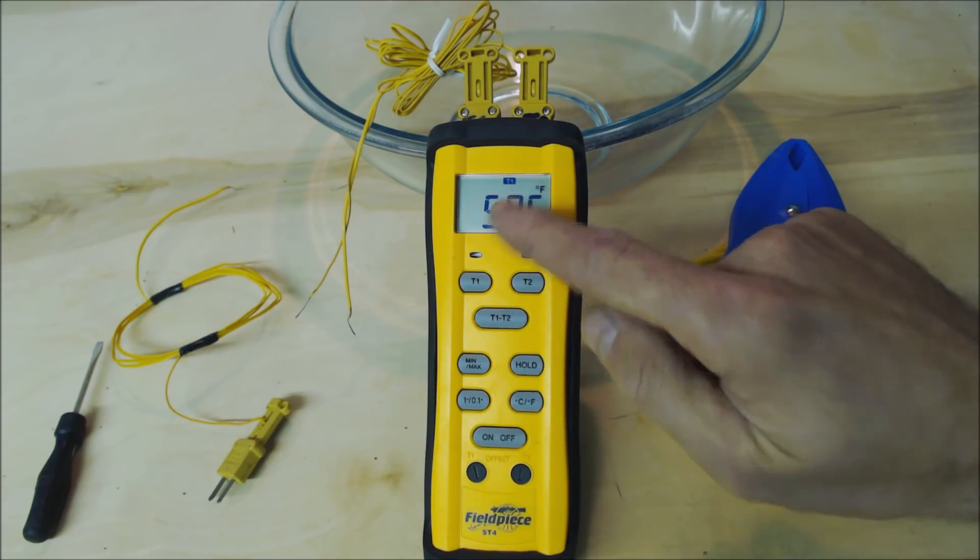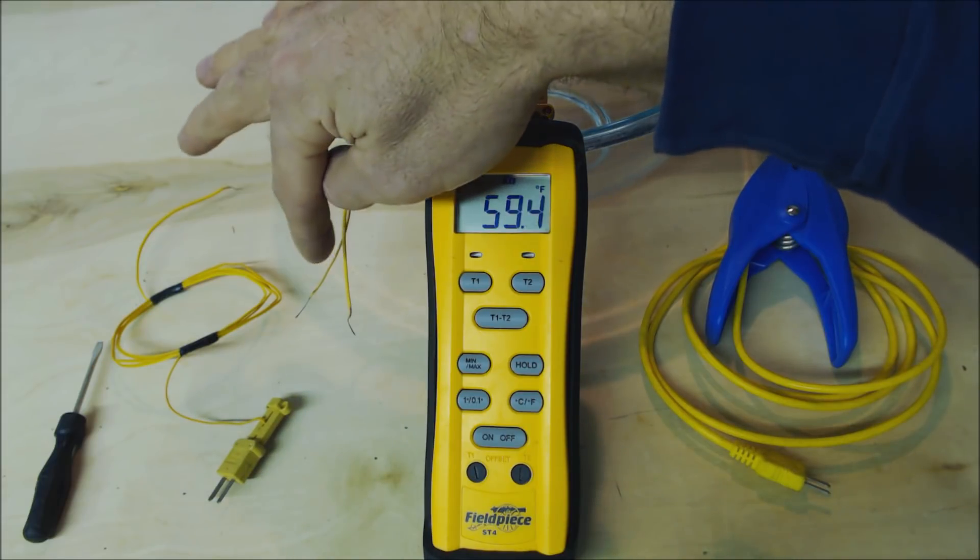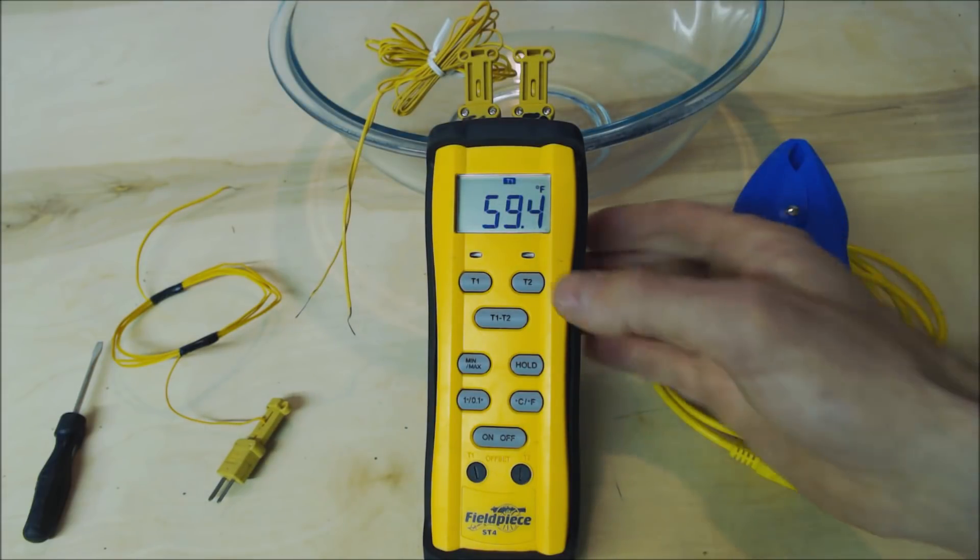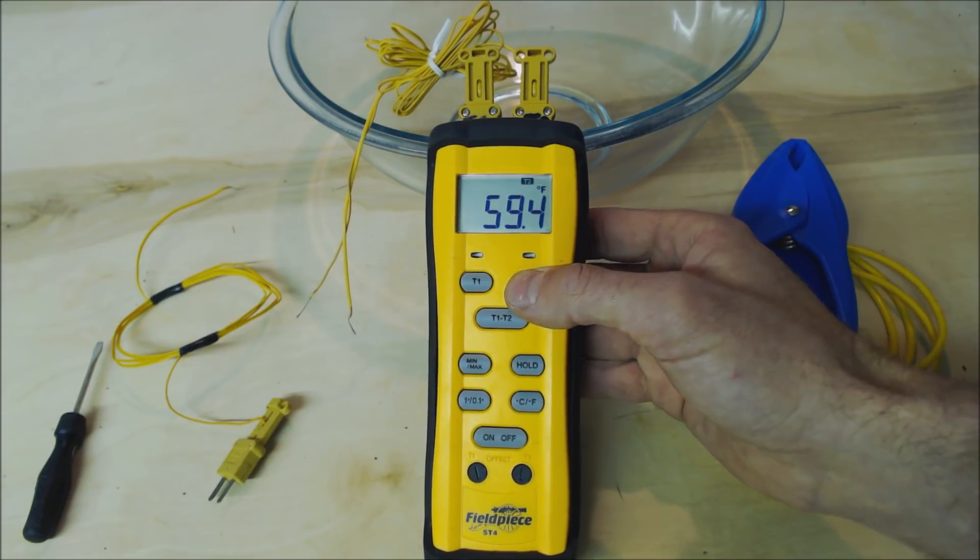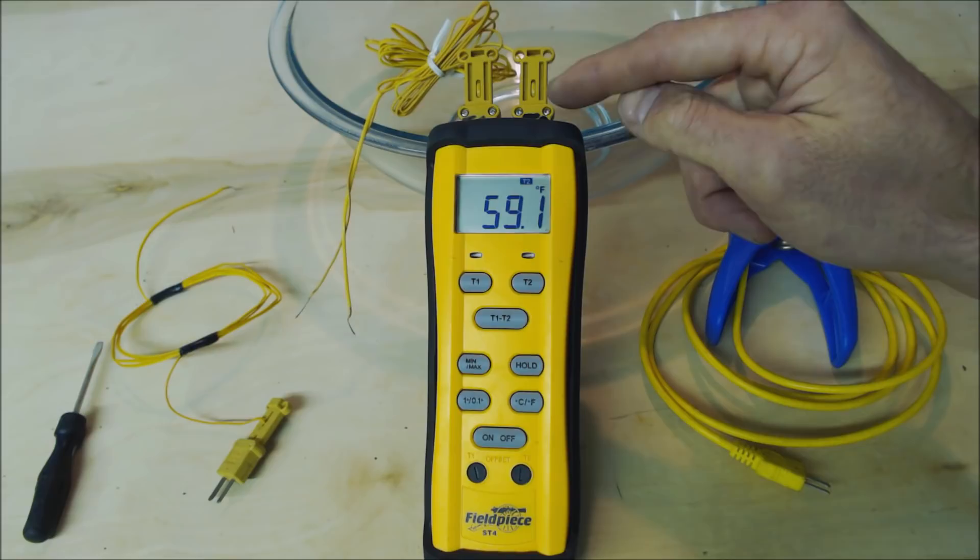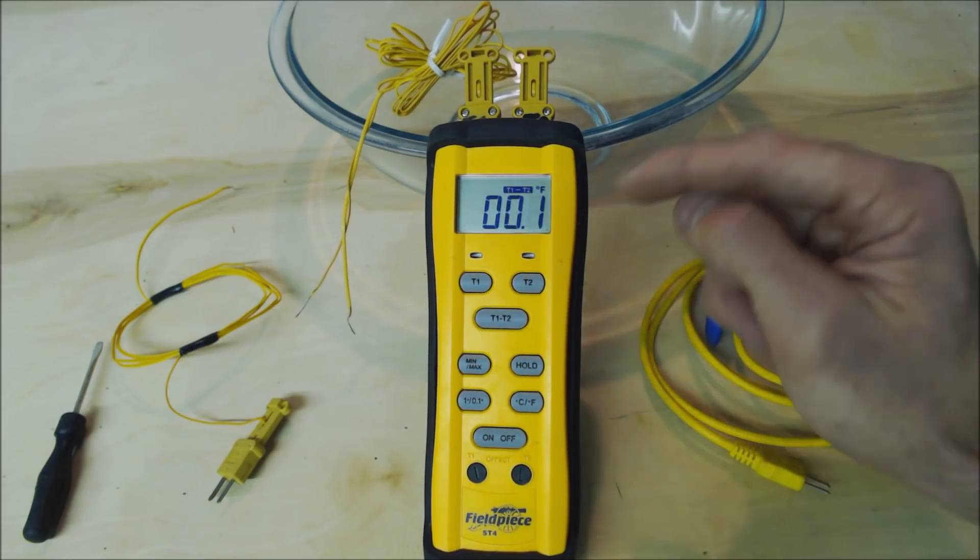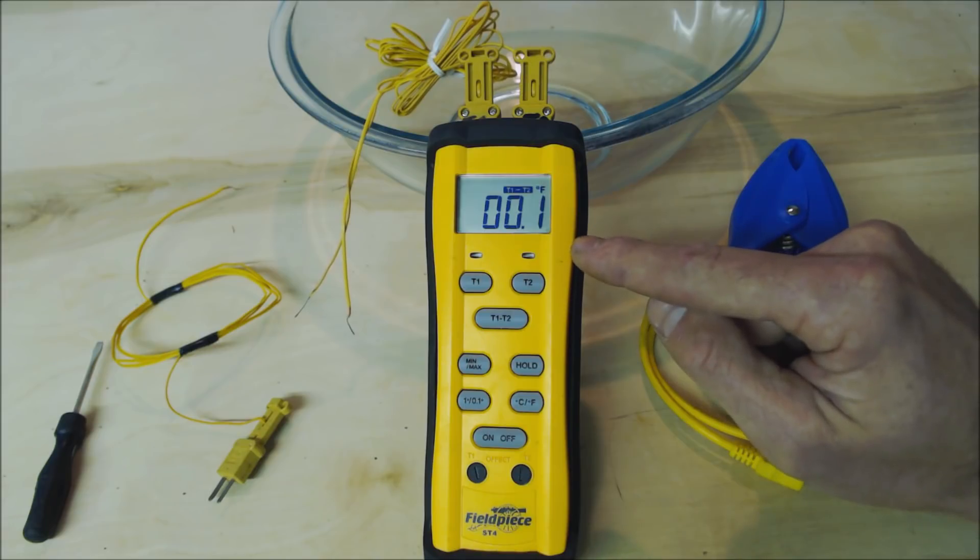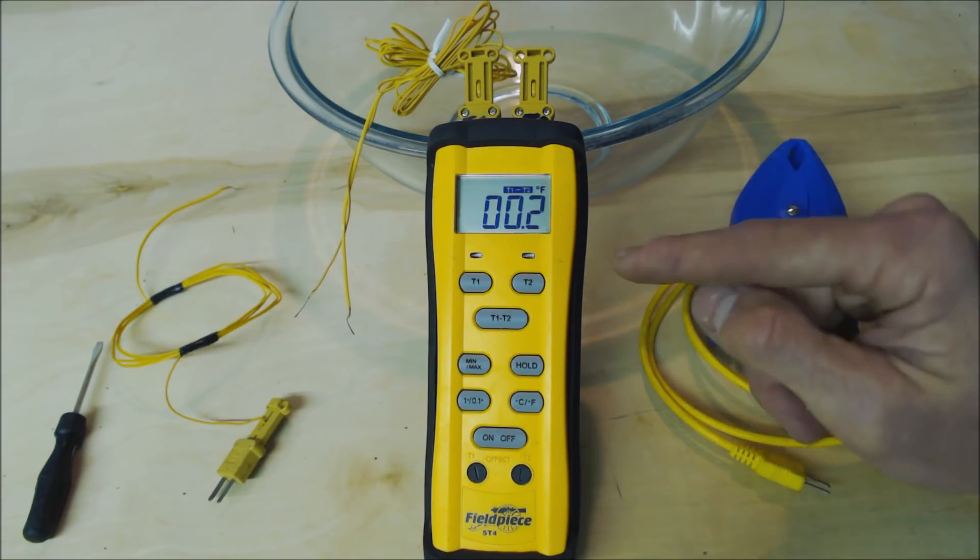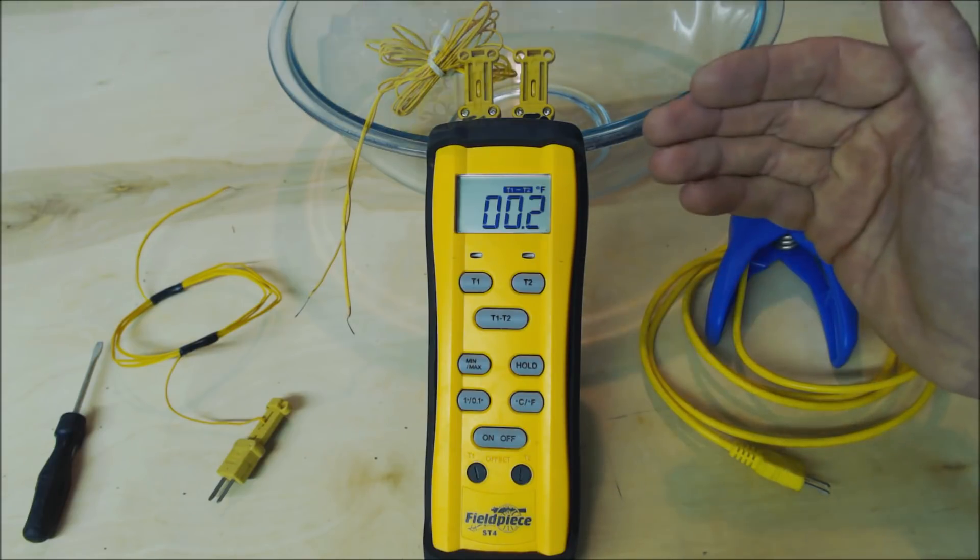Right now we are reading the two right there. I have them all kind of wound up because I want them to take the temperature reading in the same location. So you see we're reading 59.4, we change it to T2 which is this one here and we're about the same measurement. We can take a differential measurement right here and we're at 0.1, 0.2 degrees off from each other and that's very close, but the question still remains are they accurately reading the temperature.